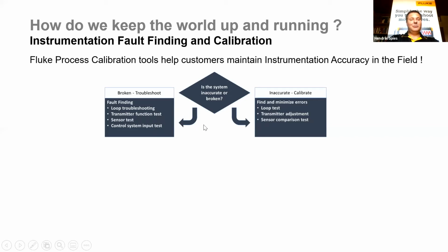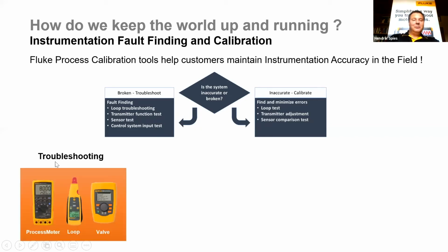So what tools are available in this portfolio? The first step would be troubleshooting. We have some process multimeters that have some loop function, but it's a fully functional multimeter. We have loop clamps. We can measure 4 to 20 milliamp voltage. But what's unique about this unit is it has a small clamp that can directly clamp on the cable to measure 4 to 20 milliamp loops. So you don't need to break the loop. You can fault find without interfering with the operation of the control system. And in this, you can do simulation measurement as well. Then we have the valve tester, which is the 710. And we also have some multifunction testers in this troubleshooting portfolio available.